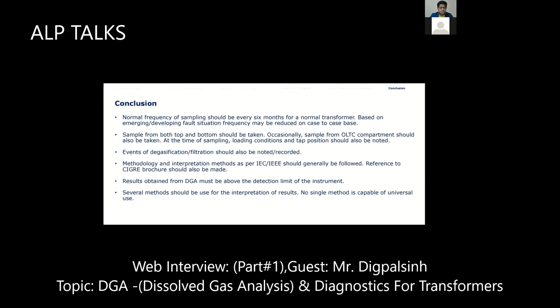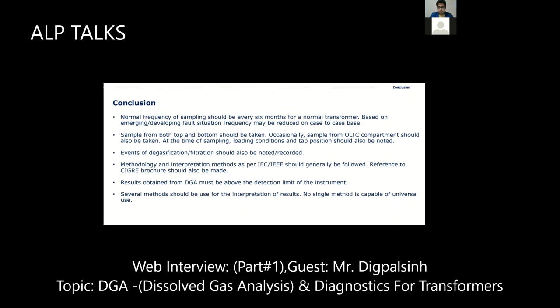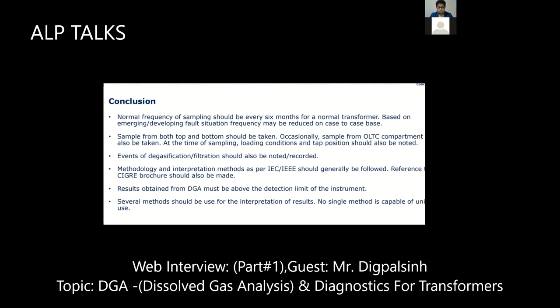And at the time of taking the sample, some customers took the sample from the top only. They found some higher gases and they are worried and come to us. What we suggest is that the sample should be taken from the top, bottom and OLTC compartment. DGA should always be done for top oil, bottom oil and OLTC compartment. So it is better to analyze its graph.